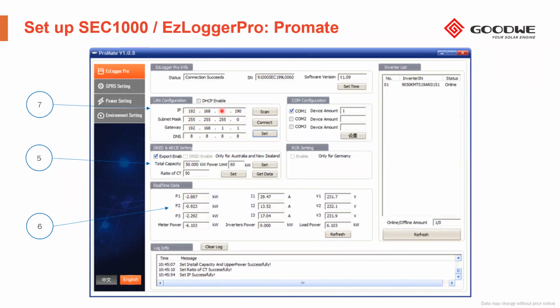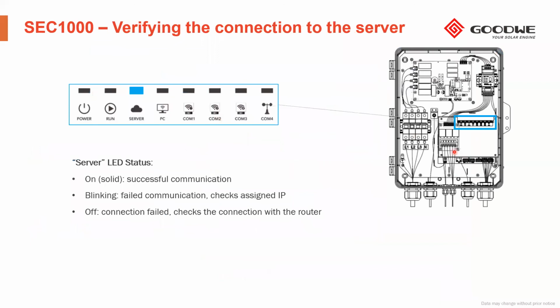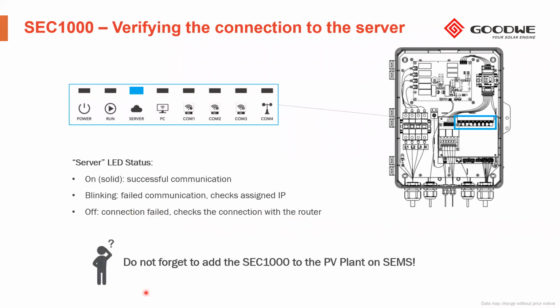And then when we finish, we connect our EzLogger Pro to the existing router by means of the Ethernet line. And then we observe after a few seconds if the server light is on, blinking, or off. If it's on, the communication has been done successfully. If it's blinking, something fails, probably the IP. And if off, we need to check all the steps that we have done because something is wrong.